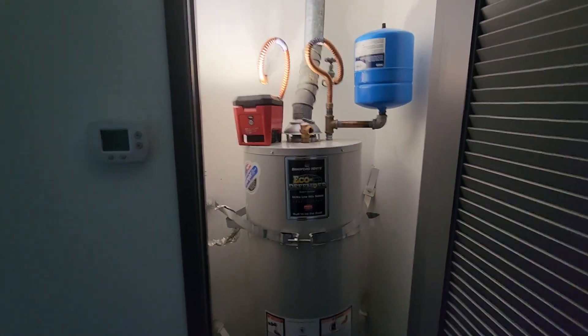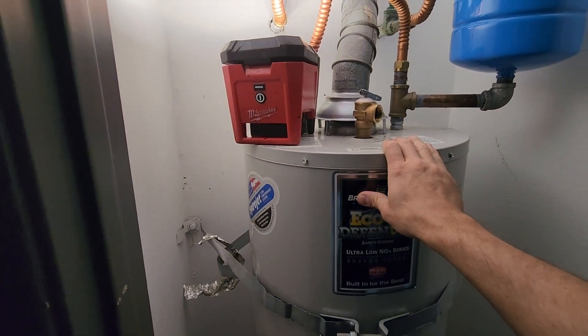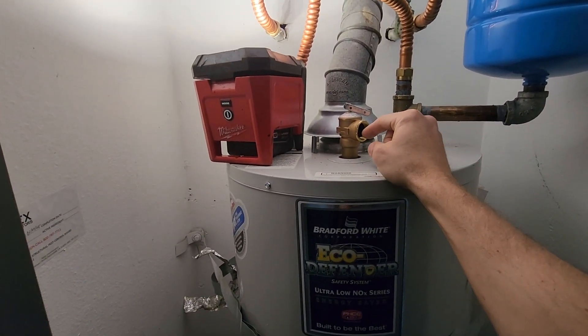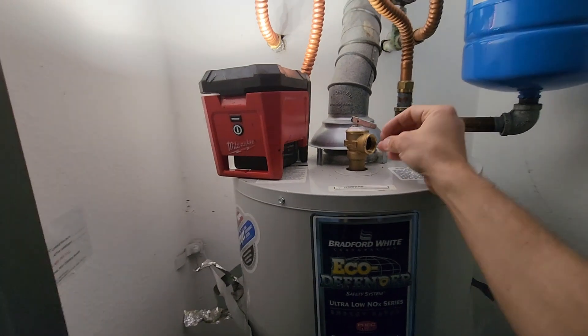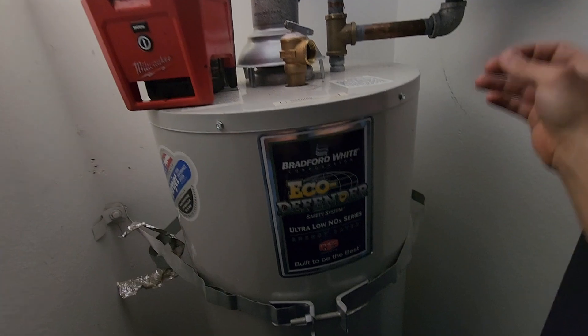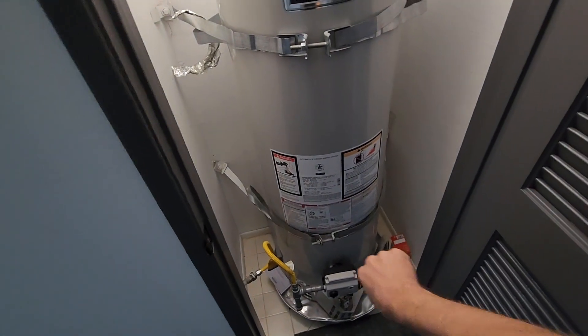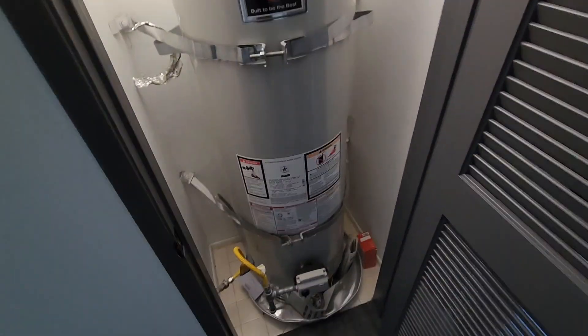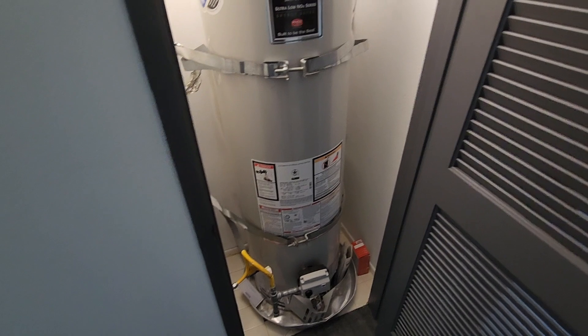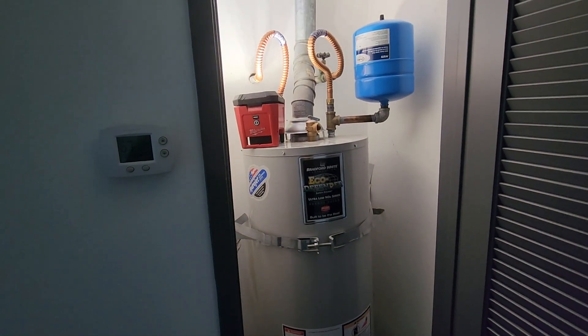If your water heater is on the first floor and near an exterior wall, code would say — at least in California, Southern California, Los Angeles specifically — they want the TPR routed six inches above the floor and then discharge to the exterior of the property and be six inches above the ground. There's a multitude of different reasons as to why inspectors want that.